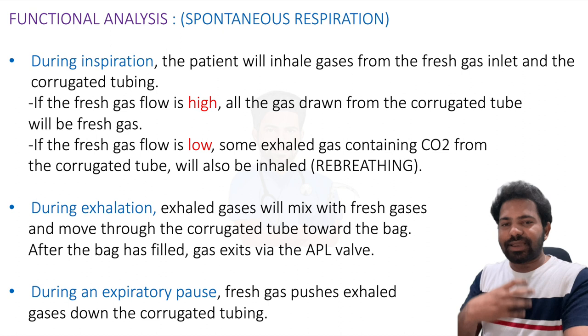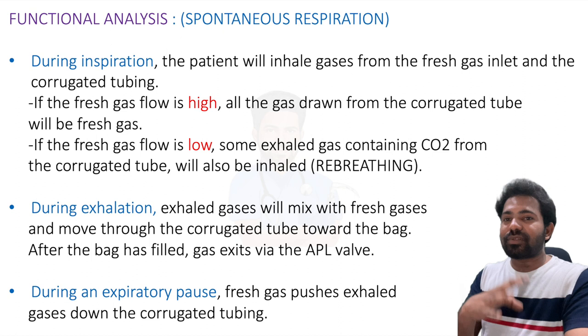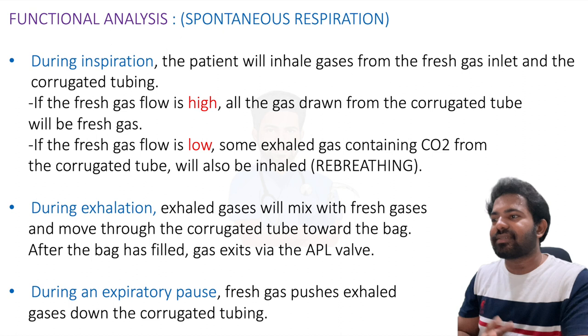Re-breathing means expired gases are again inspired by the patient — the expired carbon dioxide is re-inhaled. Re-breathing depends on the fresh gas flow: if fresh gas flow is high, there is less re-breathing; if fresh gas flow is low, there will be more re-breathing of the expired gases.